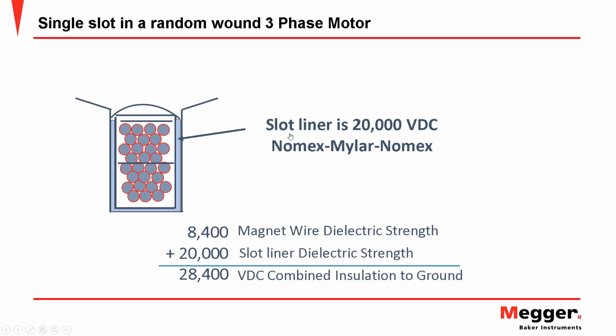And this is typically some kind of Nomex or composite material that includes Nomex, which has a breakdown voltage of as high as 20,000 volts. And we've actually done these measurements in-house in our laboratories at Baker, and this is proven out. These insulation systems are really this strong. Cumulatively then, the insulation breakdown voltage of a 460 volt motor at the beginning of its life is approximately 28,400 volts.